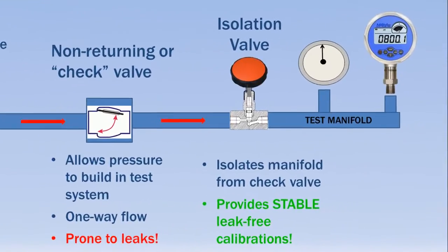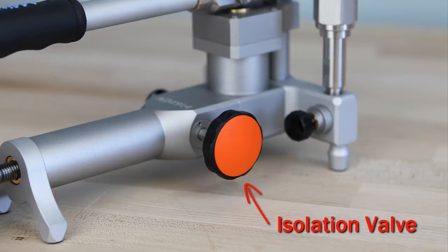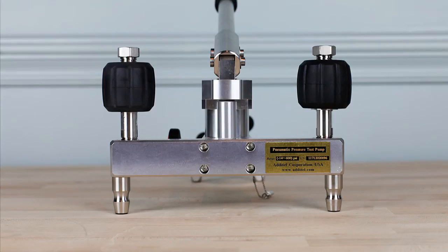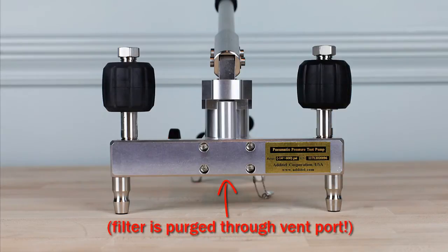Additel pumps include a valve that isolates the calibration volume from the check valve, providing stable calibrations even as seals degrade over time. The 914 and 916 pumps include particulate filters located in the manifold that protect sensitive pump components from moisture and dirt, reducing maintenance and wear.